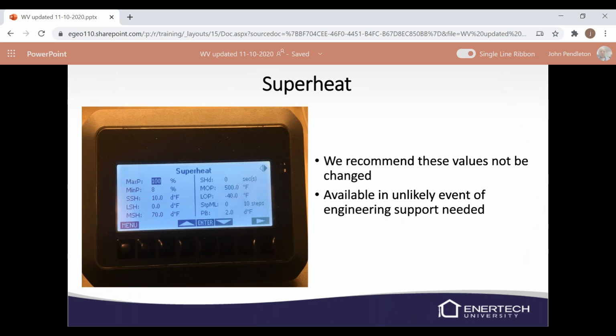We have a superheat menu. It'll show you what the superheat is set at. You can go in there and change it, but with engineering support. If you think you need to change it, call us and we'll discuss it. And if we decide that we need to change it, then we'll let you know how to do that.